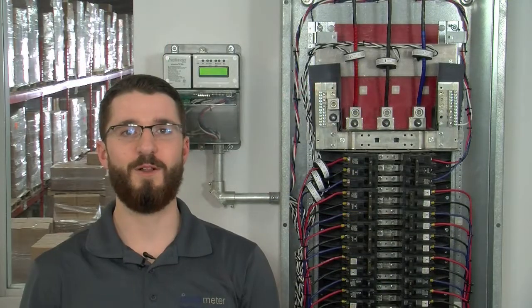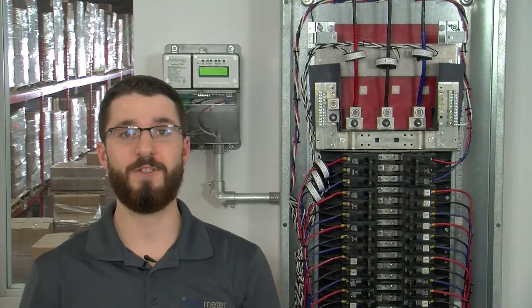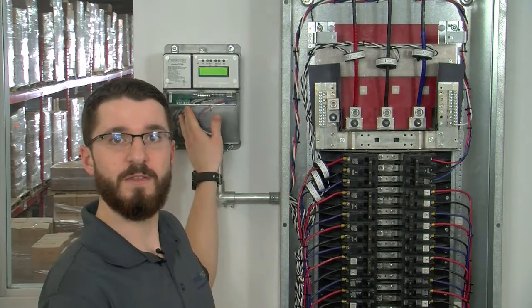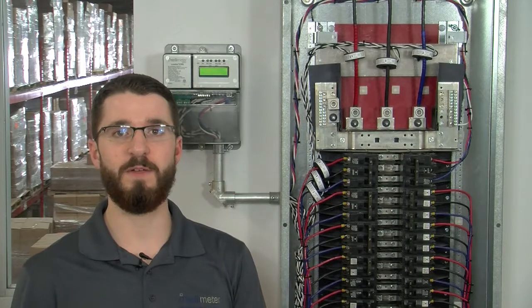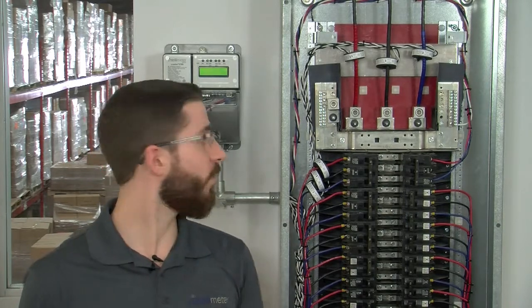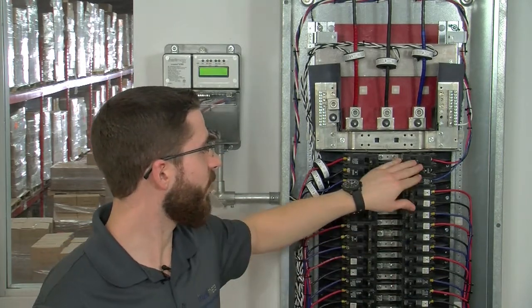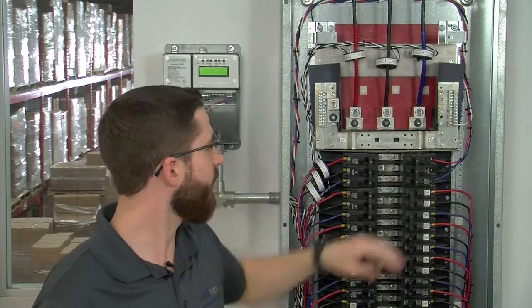Now it's time to install our reference voltage. The reference voltage is used to both power up the iMeter EM6 as well as provide the meter with reference to the different voltage phases. In order to install the reference voltage, a separate 3-pole 15 amp breaker is required.